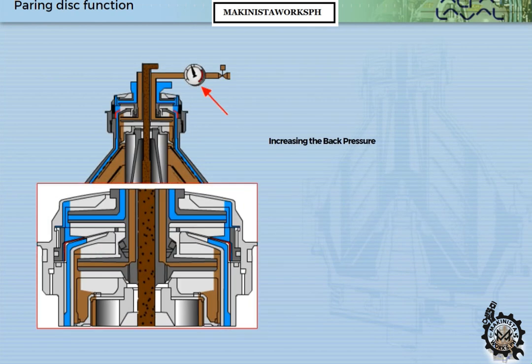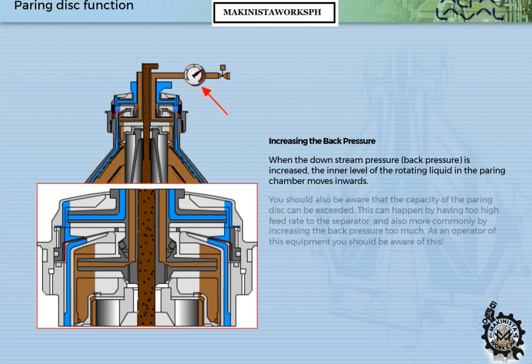When the downstream back pressure is increased, the inner level of the rotating liquid in the paring chamber moves inwards. You should also be aware that the capacity of the paring disc can be exceeded. This can happen by having too high a feed rate to the separator, and also, more commonly, by increasing the back pressure too much. As an operator of this equipment, you should be aware of this.